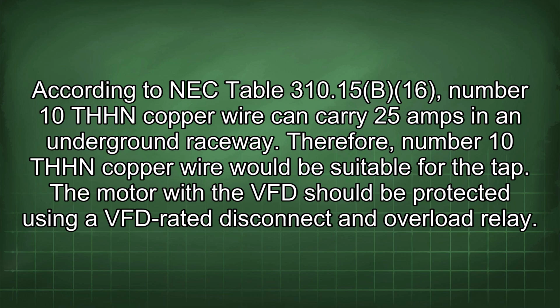According to NEC Table 310.15(B)(16), number 10 THHN copper wire can carry 25 amps in an underground raceway. Therefore, number 10 THHN copper wire would be suitable for the tap.